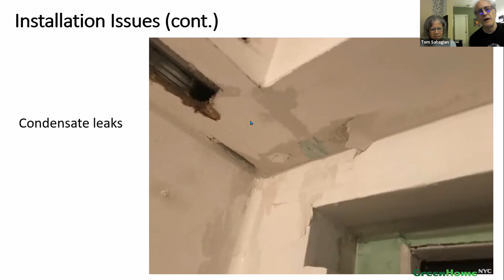The refrigerant lines come insulated, but they have to remove some of the insulation sometimes, like when sliding it through the wall. What they're supposed to do is put the insulation back on. As you can see, this happened several times, and they didn't do that. Also, because of having to drill pretty big holes in the wall to put the line set outdoors, you had exposed brick and holes passing all the way through, and water, if it rained outside, could leak in.